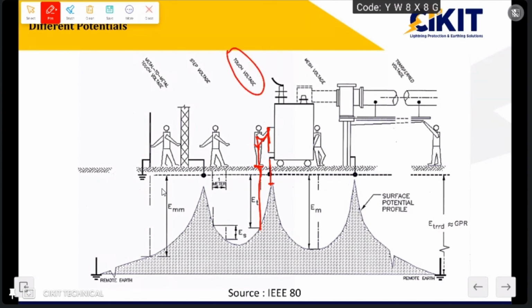For this potential to cause damage, we have to make contact with the grounded object. The second one is the step potential. In this case, there is no direct contact between the person and any structure. If you closely observe, this point is grounded and hence this point will be at higher potential and the potential is reducing. So the first foot will be at higher potential and the second foot at lower potential. Because of this difference in potential, current will flow through the body and the person will get electrocuted. For step voltages, there is no need for direct contact. Even without direct contact, he may get electrocuted if there is a sufficient potential between these two feet.